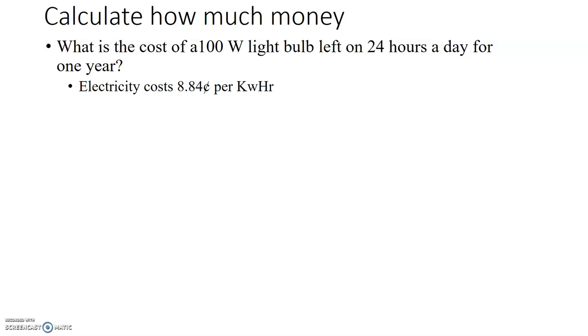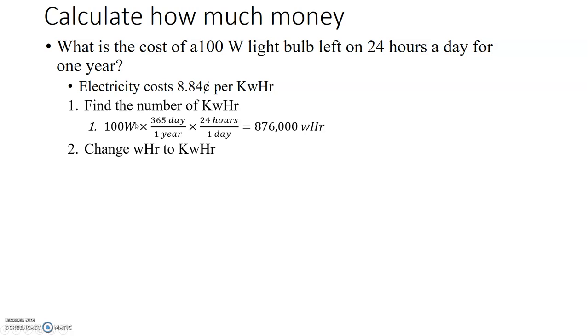Now how do we calculate how much money? What's the cost of a 100 watt light bulb left on 24 hours a day for one year at the cost of 8.84 cents per kilowatt hour? First, we need to figure out how many kilowatt hours there is. We take our 100 watts and multiply that by how many hours is in a year. So 365 days times 24 hours, that gives me 876,000 watt hours. Now we need to change that wattage to kilowatts, so we divide by a thousand. That becomes 876 kilowatt hours.